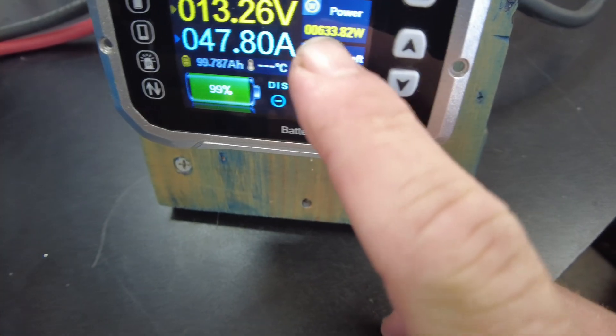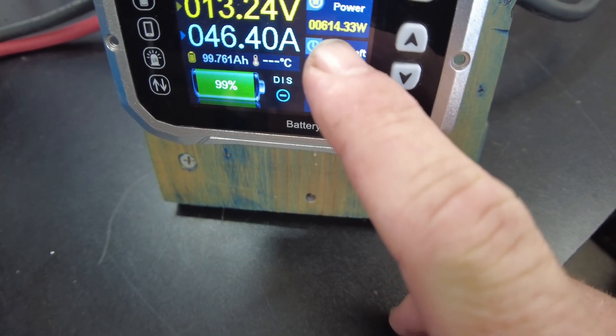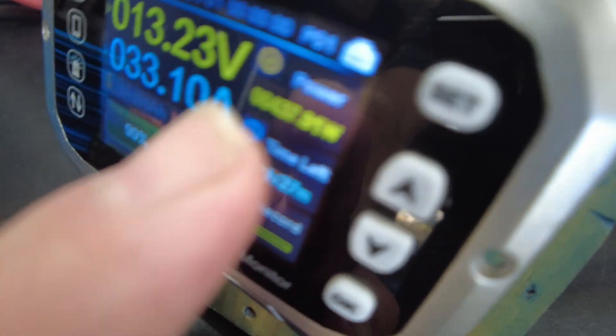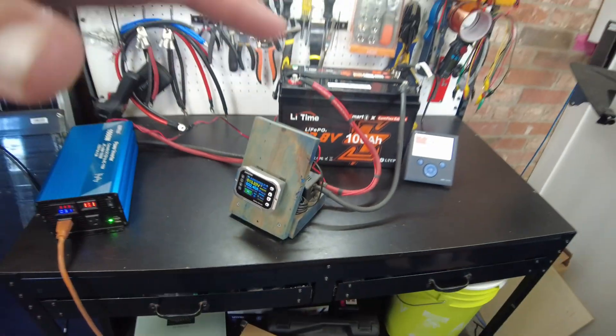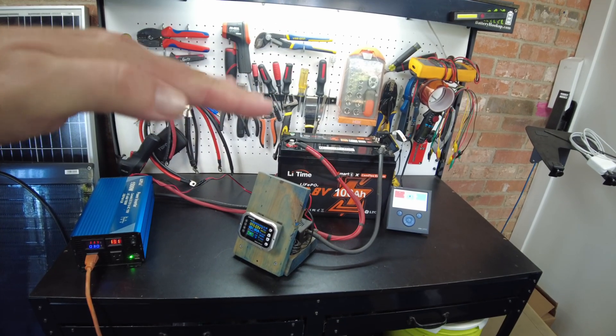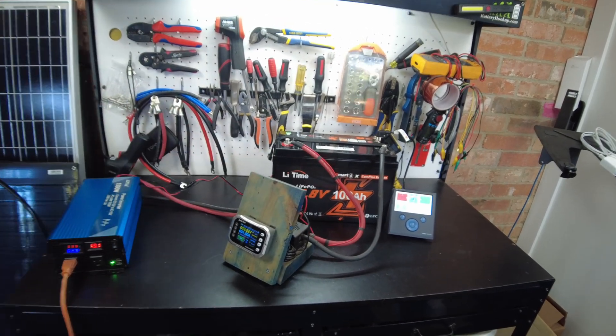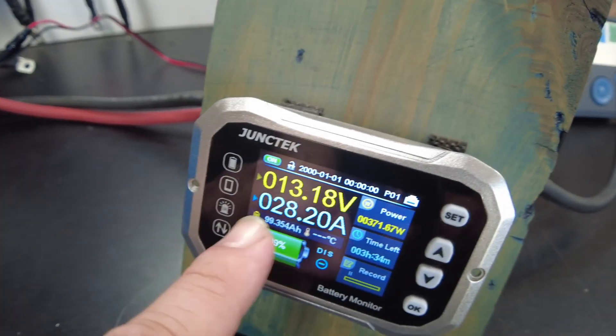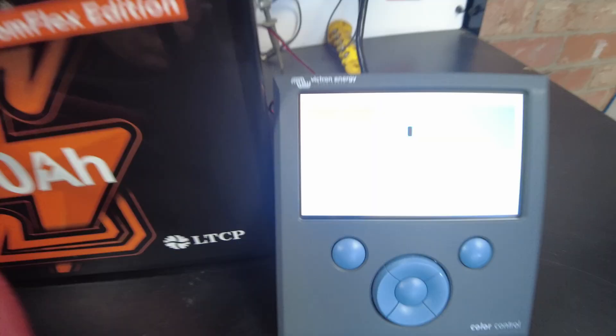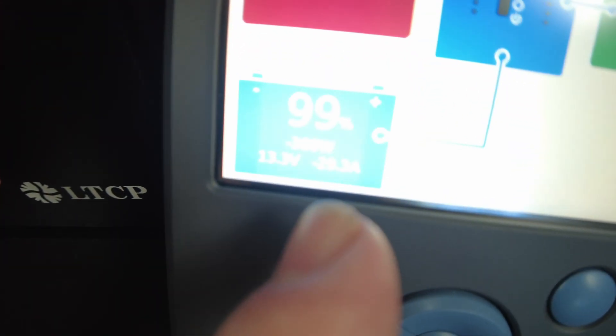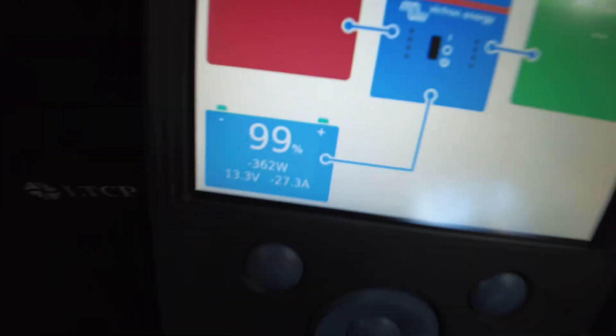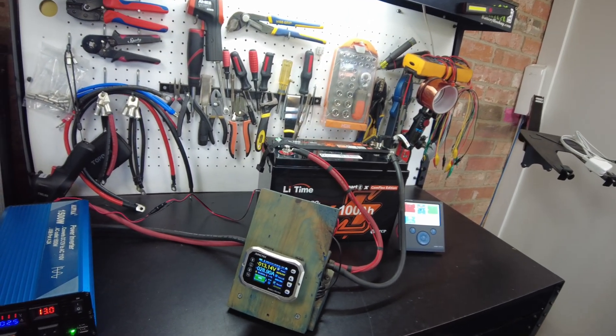So currently we are drawing 630 watts according to this shunt. This one's currently saying about 500 watts. I think it's gone down a little bit. Yeah, we are actually going down, it's saying 430. It's because the air conditioner starts up a little bit higher and then starts to kind of simmer down. Looks like we're pulling 28.5 amps, showing about 27.8, 29 amps here. All right, I'm gonna let it keep running and I'll be back.